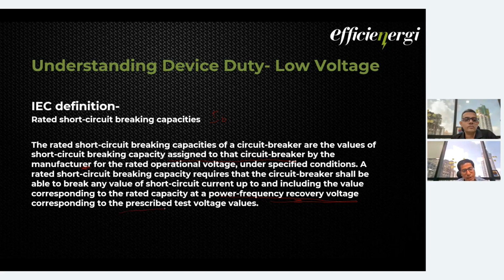Then again the same prescribed test voltage values. So test voltage values can be anything, because all the labs may not have a 440 volt setup, they might have a 230 volt setup. So the manufacturer gives all the values for all the voltages. If you look in the data sheet, it starts from 230 volts, then 440, and goes up to 690 volts.